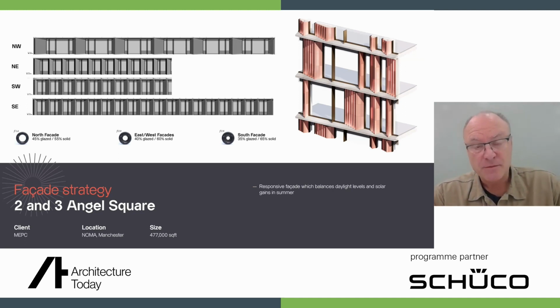So as you see, the top strip of facade there, northwest facing, which luckily for us faces the main square, we can have more glazing. And then with the southwest and southeast facades, you'll see there's less glazing and more solid. So the facade is highly responsive to its orientation and the solar gain load on that elevation. And we know from past experience that the cooling load in a modern office building, at least 50% of that total cooling load comes from solar gain, as internal heat gains from computer screens and lighting continues to fall. So any office building that ignores orientation is ludicrous really in this day and age, and there's no excuses for putting style and appearance before this approach to drive down energy consumption.